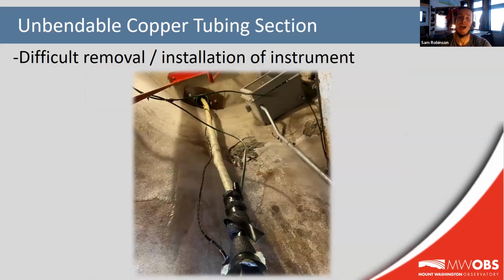So along the same lines of tubing length comes the second area for improvement, which is ease of removal and installation of the instrument from the top of our instrument tower. The first 10 feet or so of pressure line coming out of that pitot tube itself is stiff copper tubing. After that 10-foot section of copper tubing, it then connects to plastic pneumatic tubing, which then carries it the rest of the way down. It is easy enough to disconnect the pneumatic lines from the copper tubing, but then you're still left with 10 feet of copper tubing from the anemometer that can't be disconnected when the instrument needs to be removed.